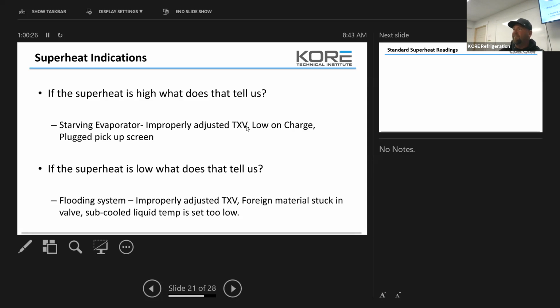If you cannot find the manufacturer's setting, instead of just leaving it because you don't know, I would rather you follow the rule of thumb. At least we're getting somewhere in the range. I don't want you to walk away without doing some kind of calibration if you suspect that you need to calibrate the expansion valve. Okay.